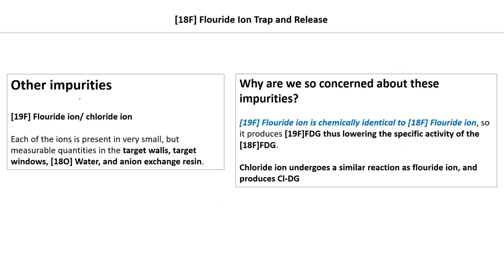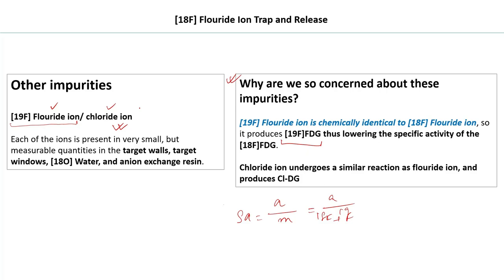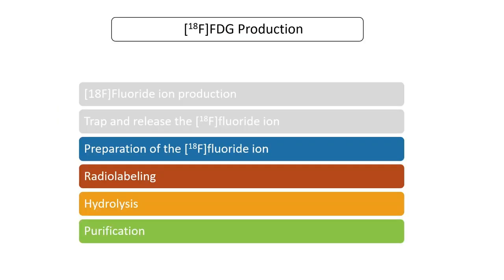Other impurities of concern are F-19 fluoride ion and chloride ion, present in small but measurable quantities in the target walls, target window, O-18 water, and anion exchange resin. F-19 fluoride ion is chemically very similar to F-18 fluoride ion, so it also produces F-19 FDG, which lowers the specific activity — since specific activity is activity per unit mass, having both F-18 and F-19 in the mass decreases it. Chloride ion undergoes similar reactions and produces chlorodeoxyglucose, reducing the yield of the final F-18 FDG product.